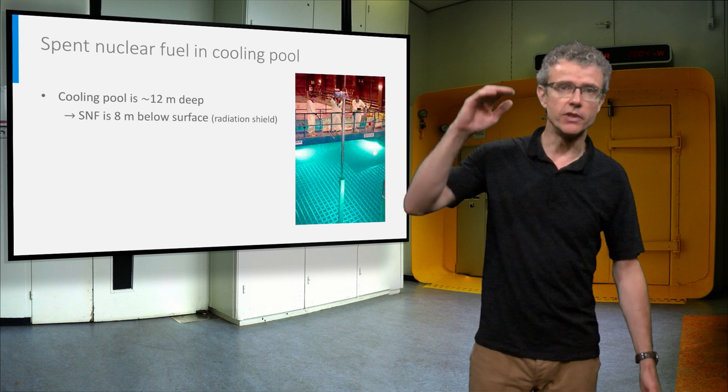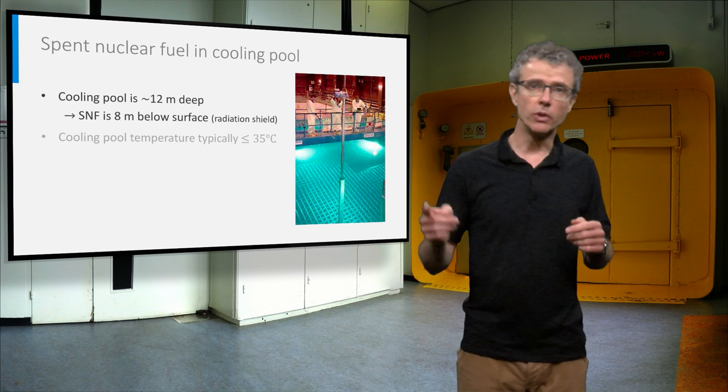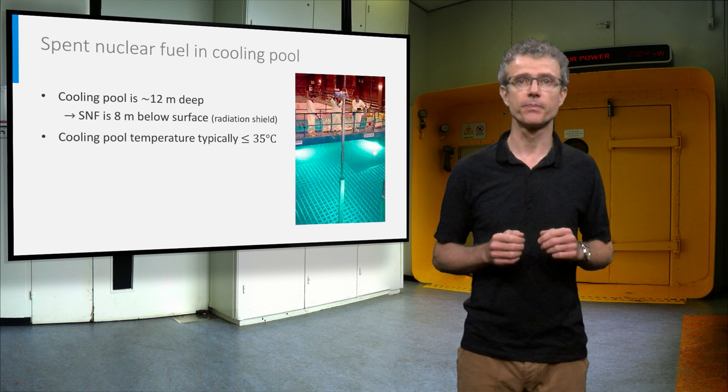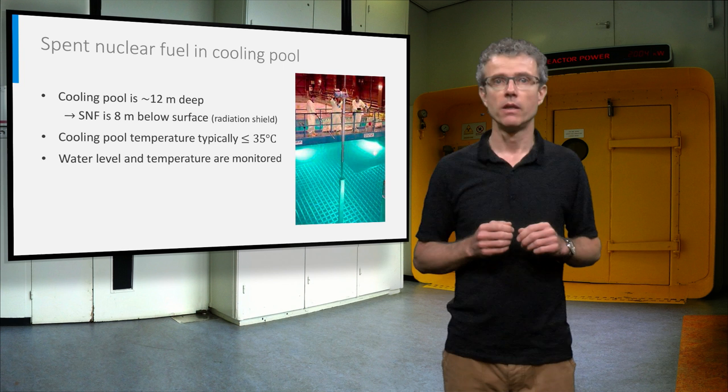A typical cooling pool is about 12 meters deep, so that the spent nuclear fuel is 8 meters below surface. The water functions as radiation shield and as coolant. A water cooling circuit keeps the pool temperature typically below 35 degrees Celsius. Water level and temperature are carefully monitored, and hydrogen detectors near the pool check for radiolysis of the water.